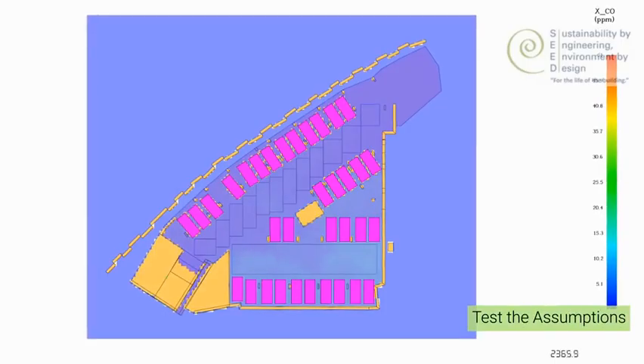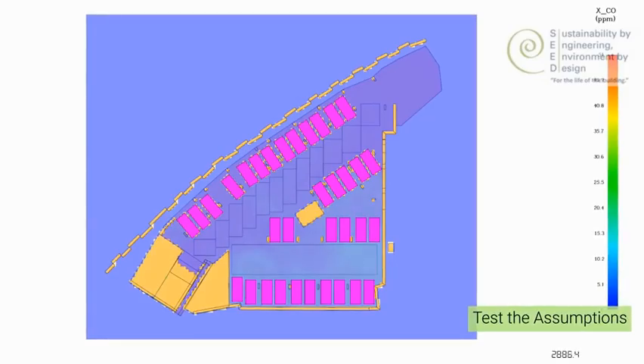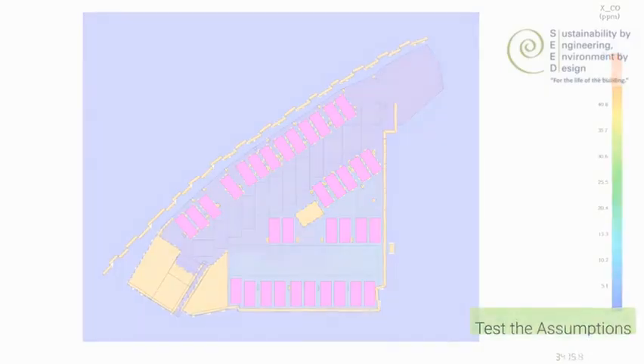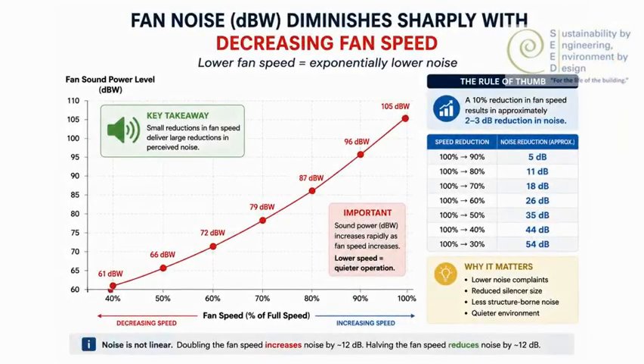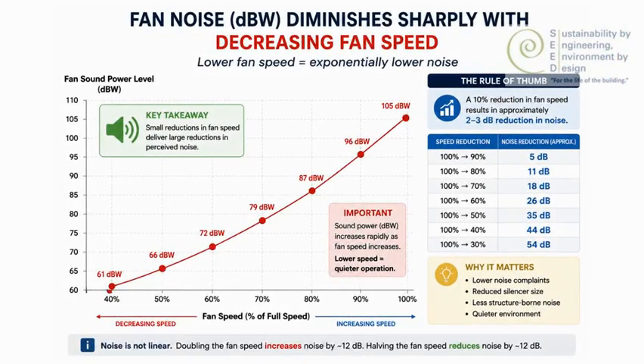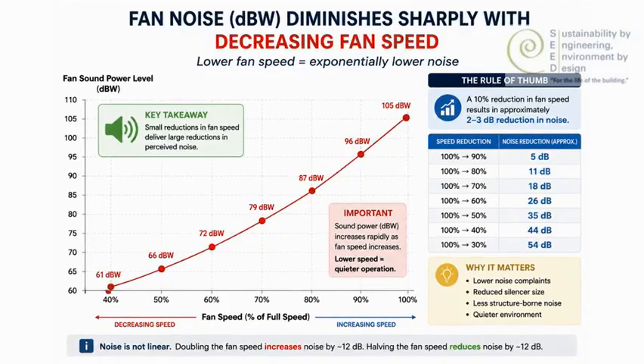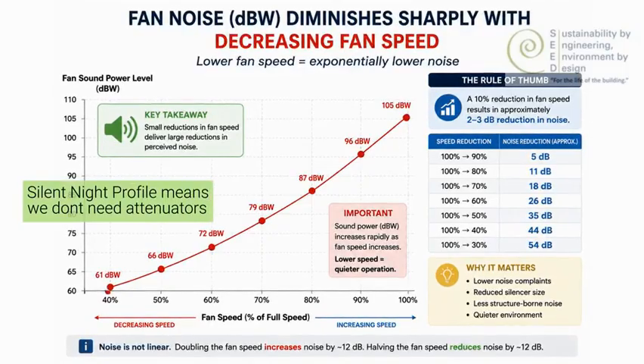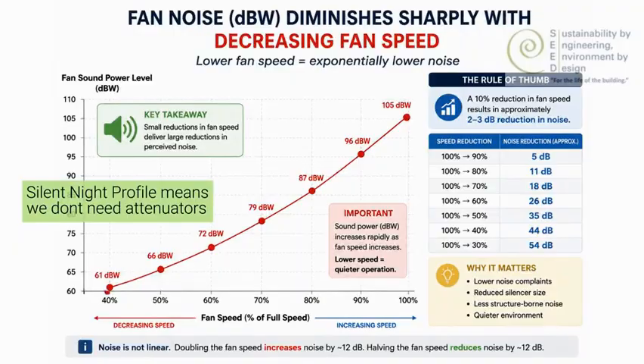One of the other valuable things we can do here is use the variable speed drives associated with these fans to lower noise. This is important because if we can remove attenuators and remove ductwork, then we can have very short and small discharges. By lowering the speed to 50%, we're achieving in the order of 12 to 18 dB reduction.